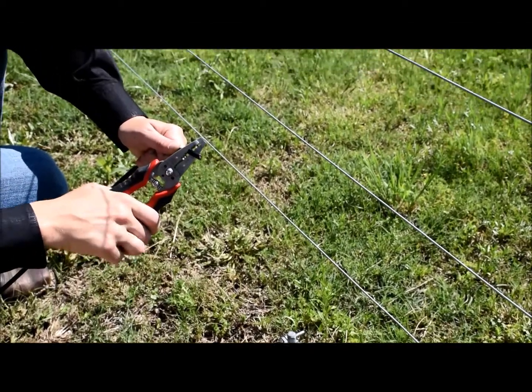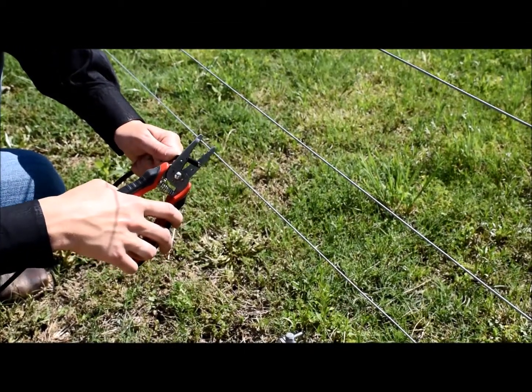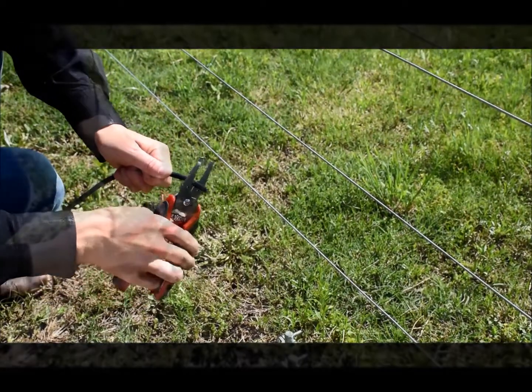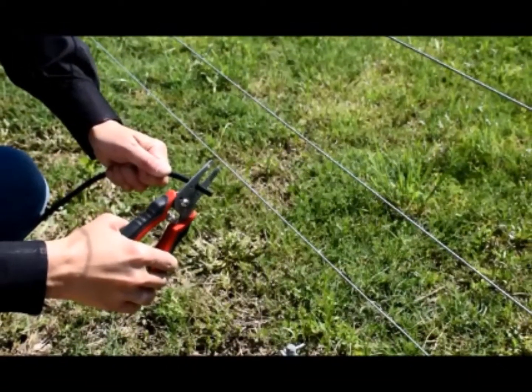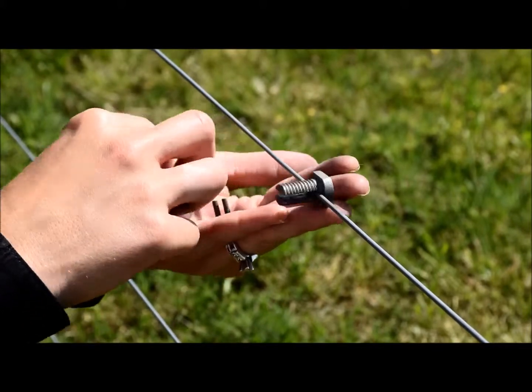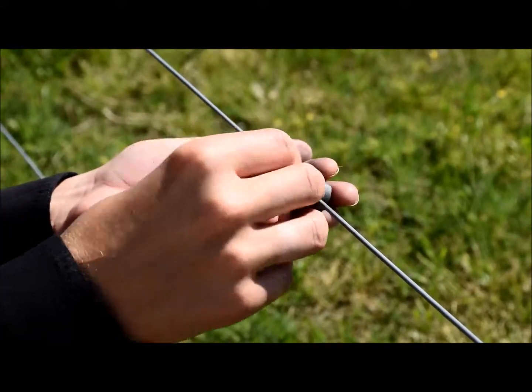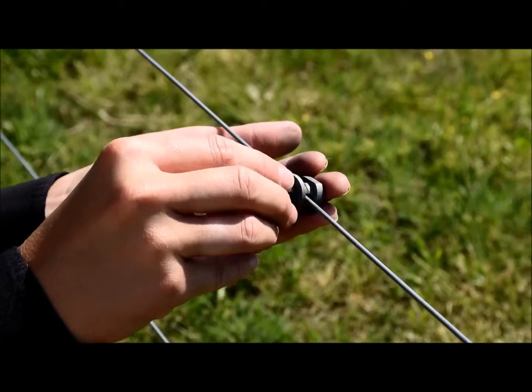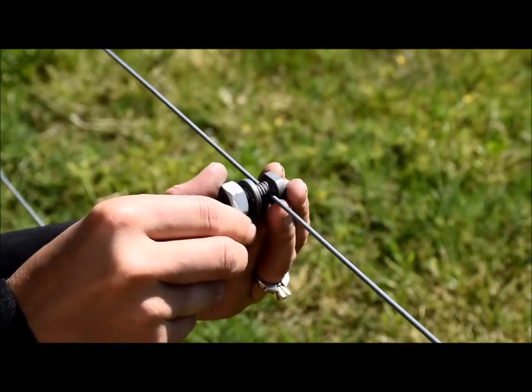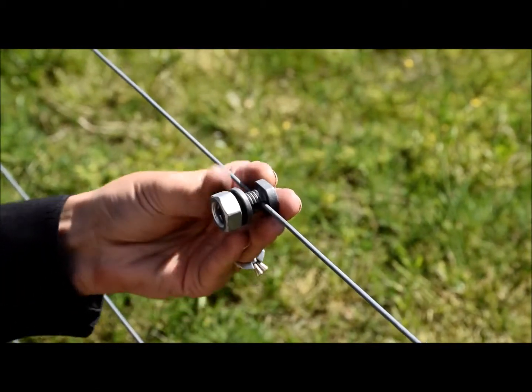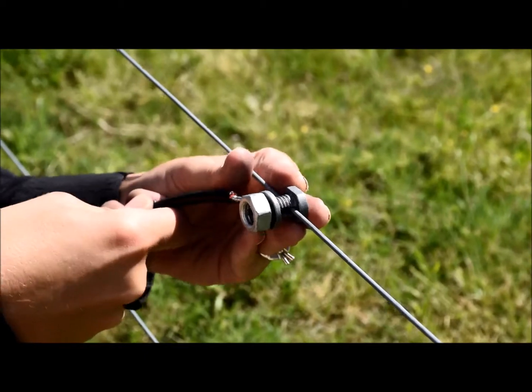Ensure you have plenty of underground cable to reach the fence, and then cut the cable. Strip away about 1 inch of coating. Remove the nut from the joint clamp and place the bolt section of the joint clamp onto the fence wire. Place the exposed end of the underground cable into the bolt section of the joint clamp so that it is parallel to the fence wire.